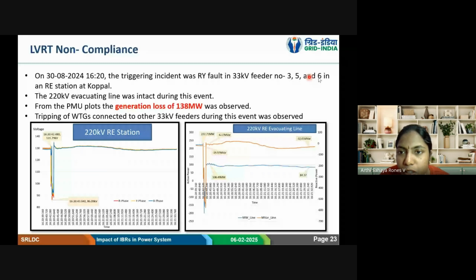There were three 33 kV feeders that had a fault. Anyway, when they got tripped, some amount of megawatt will go. But beyond that, additionally, we have seen the WTGs getting tripped for the fault in the feeders. Only when there is a fault in the WTG should it trip. For a fault in feeders, when the voltage is within the LVRT limit, the WTGs are not expected to trip. So in this case, we have observed tripping of the WTGs.